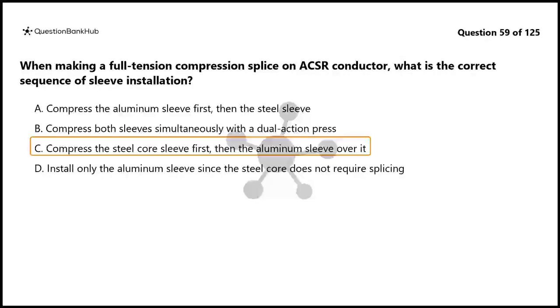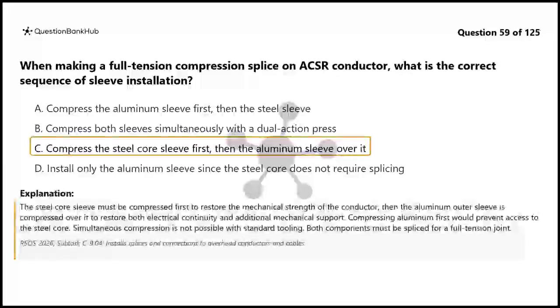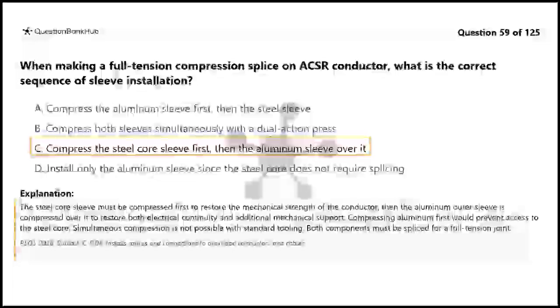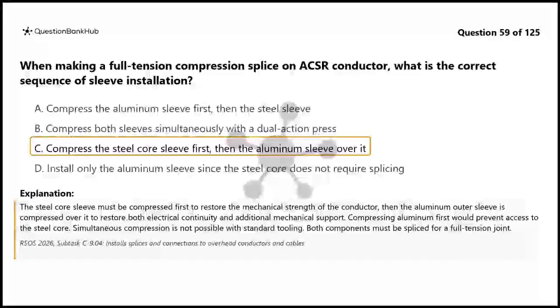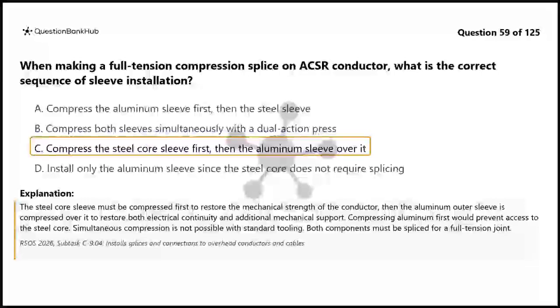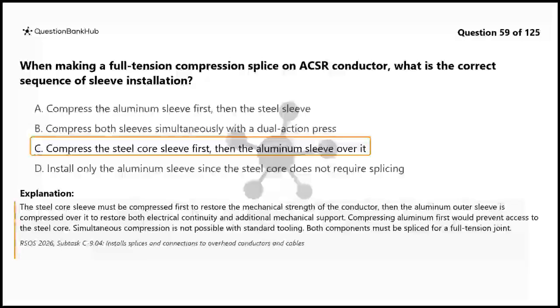The correct answer is C. The steel core sleeve must be compressed first to restore the mechanical strength of the conductor, then the aluminum outer sleeve is compressed over it to restore both electrical continuity and additional mechanical support. Compressing aluminum first would prevent access to the steel core. Simultaneous compression is not possible with standard tooling. Both components must be spliced for a full tension joint.